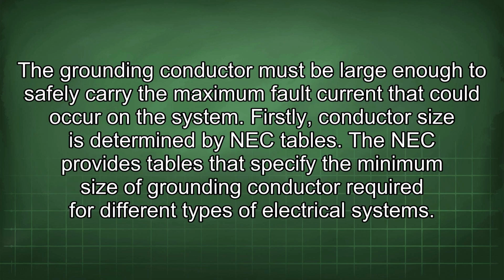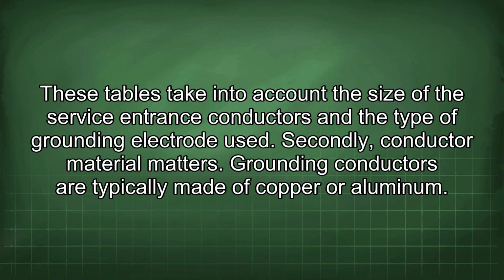The grounding conductor must be large enough to safely carry the maximum fault current that could occur on the system. Firstly, conductor size is determined by NEC tables. The NEC provides tables that specify the minimum size of grounding conductor required for different types of electrical systems. These tables take into account the size of the service entrance conductors and the type of grounding electrode used.